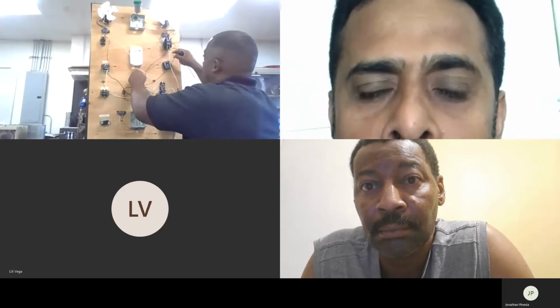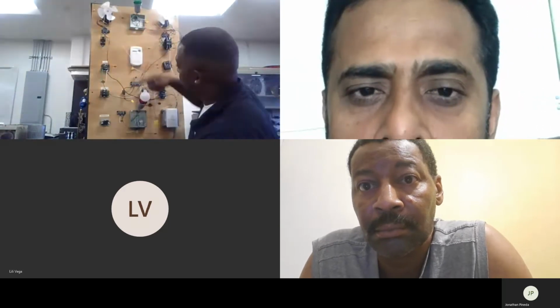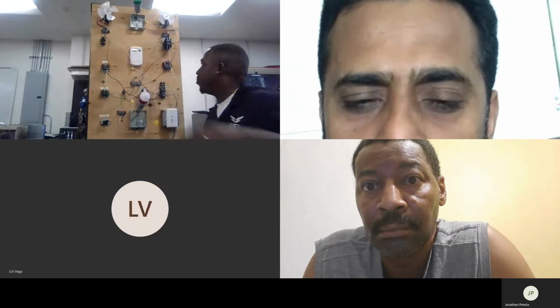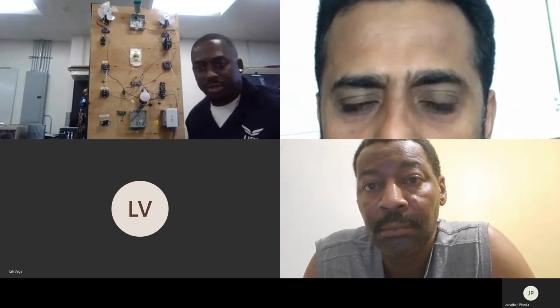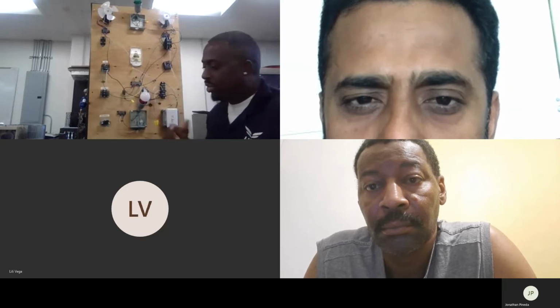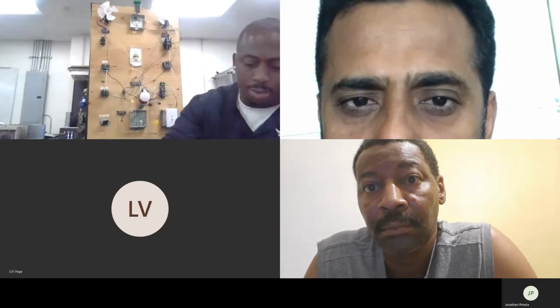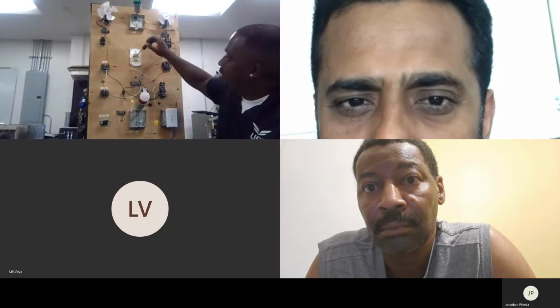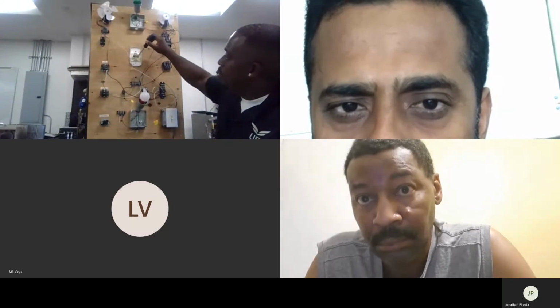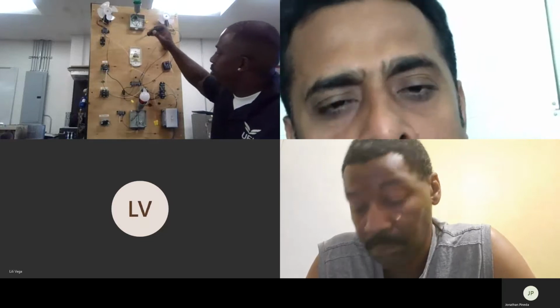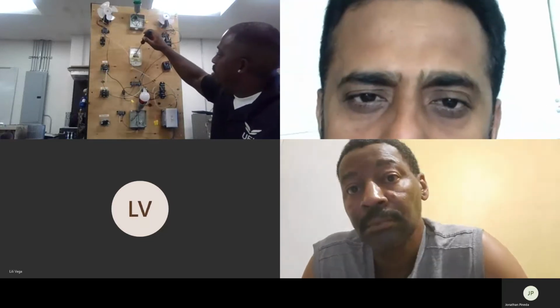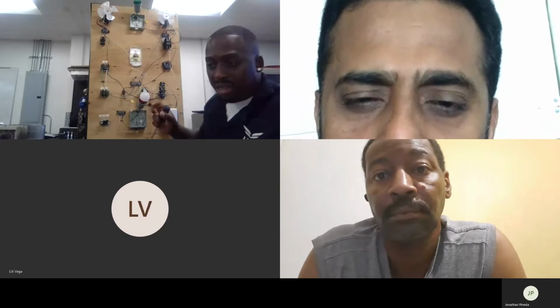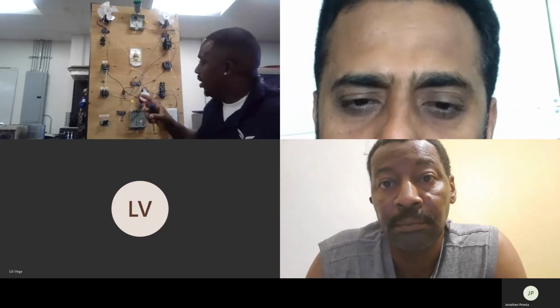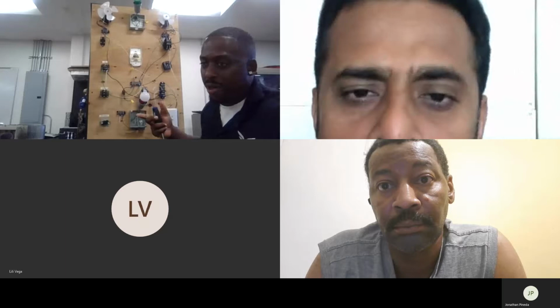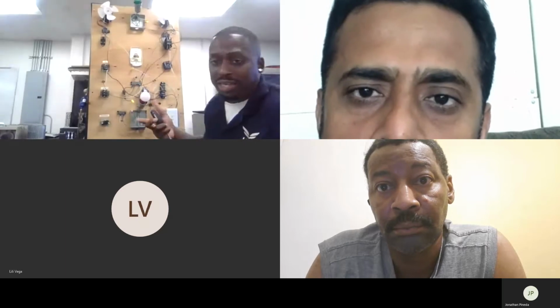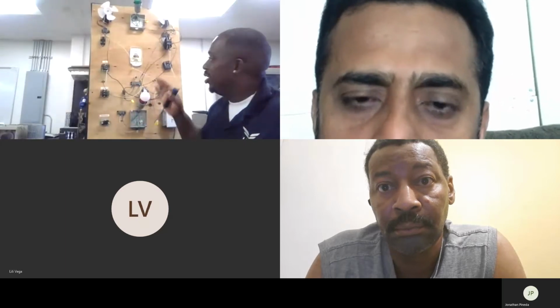Then we have our common for our contactor coil and our Y. So again, just a quick recap, or maybe for the first time for someone: R, Y, G, all these letters I keep referencing are the thermostat terminals. Every one of these terminals is marked. That one's a Y. We have an O and a B, which is for heat pumps, something we'll deal with in the future. We have a W, an R, and a G. I don't know how they got those designations. I don't know why R isn't just 24, since that's our 24-volt supply. I don't know why Y is Y and not C, since that's for cooling. Whatever the case, that's what those are.